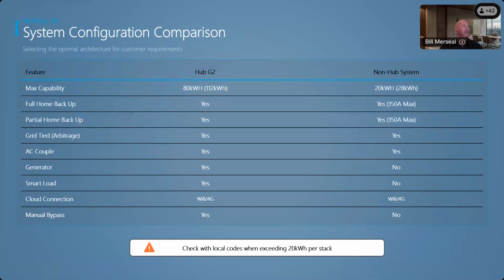Okay. So can you do a whole home backup with a non-hub system? It does show a yes here, but here's what I will tell you. The hardware size of that inverter, right? If you're going to do a full pass-through, a lot of times you're going to use a 2-aught wire on that size. It's the terminals. We don't have the terminal size that has the capacity. So unless it's going to be an off-grid system, off-grid's not a problem. But if you're doing a grid-tied system, that 150 to 200 amp service has a certain gauge wire, and unfortunately the terminals on the inverter don't have the right size ports for that gauge.